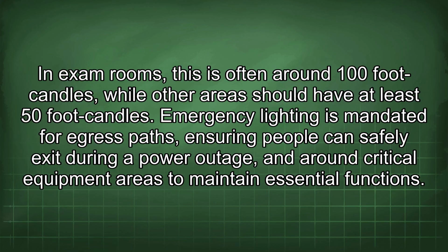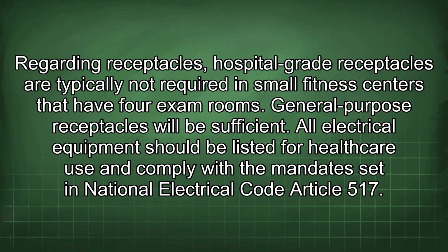Emergency lighting is mandated for egress paths, ensuring people can safely exit during a power outage, and around critical equipment areas to maintain essential functions. Regarding receptacles, hospital-grade receptacles are typically not required in small fitness centers that have 4 exam rooms. General-purpose receptacles will be sufficient.